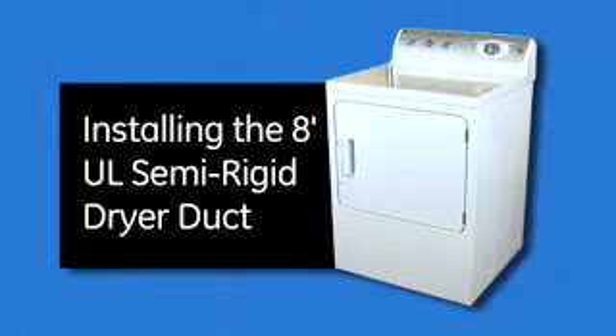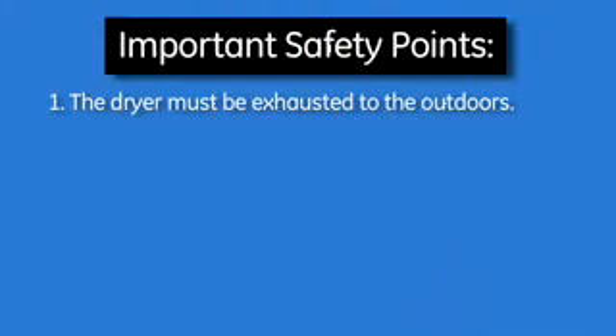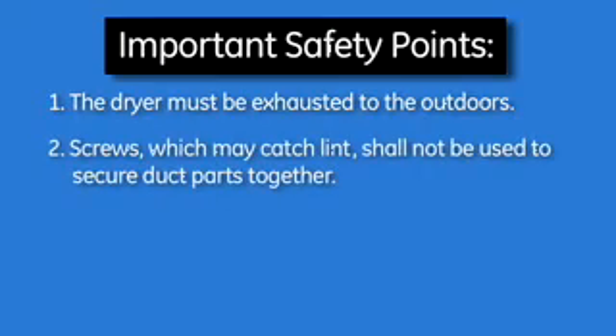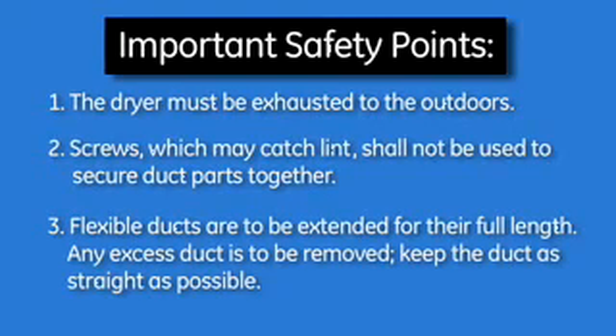Installing the 8-foot UL semi-rigid dryer duct. To reduce the risk of fire or personal injury, it is important to adhere to all of the following points when installing the 8-foot UL semi-rigid dryer duct. The dryer must be exhausted to the outdoors. Screws, which may catch lint, shall not be used to secure duct parts together. Flexible ducts are to be extended for their full length. Any excess duct is to be removed. Keep the duct as straight as possible.